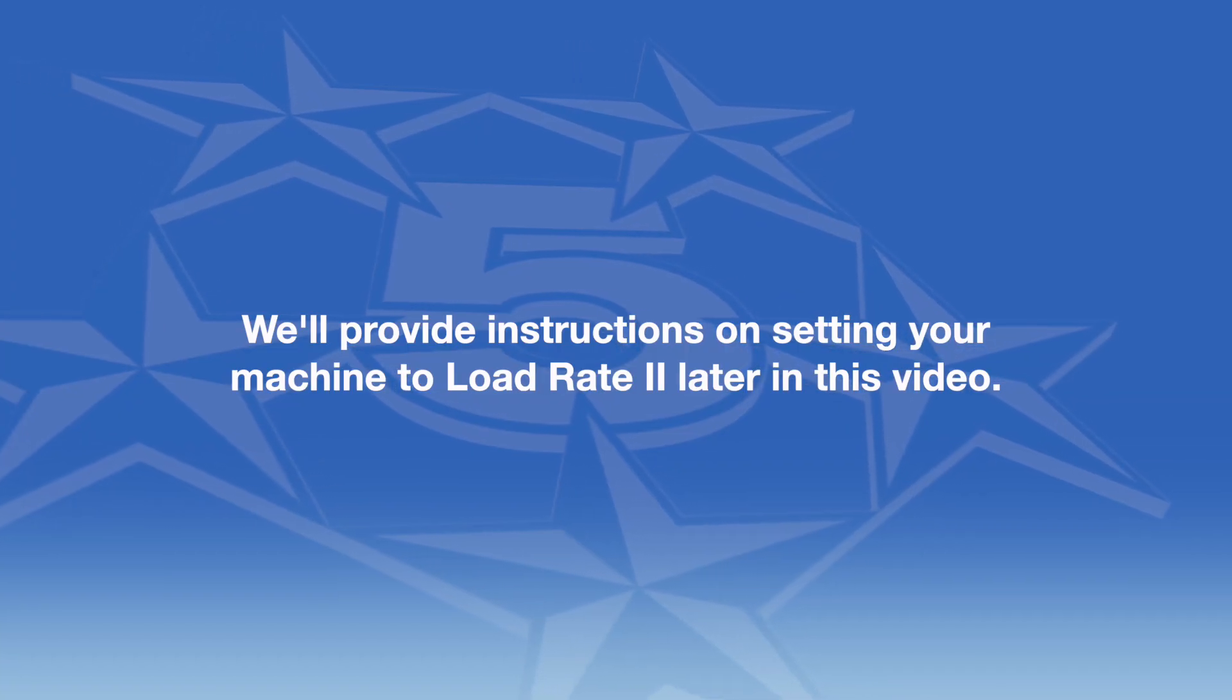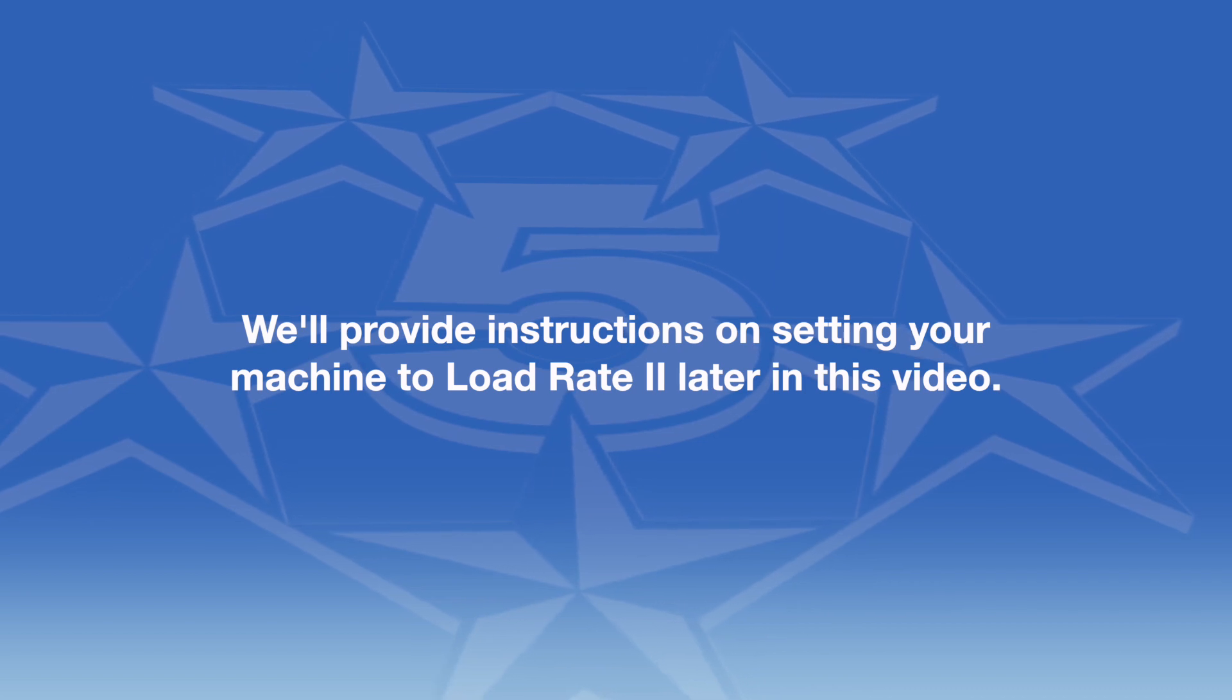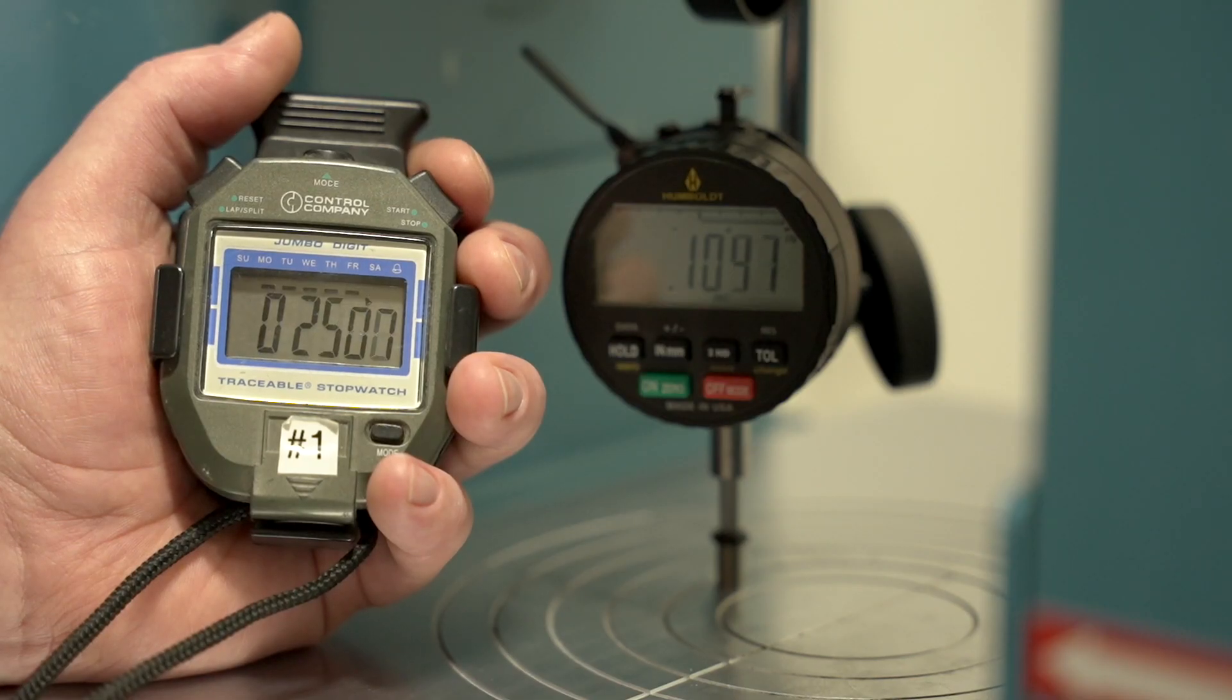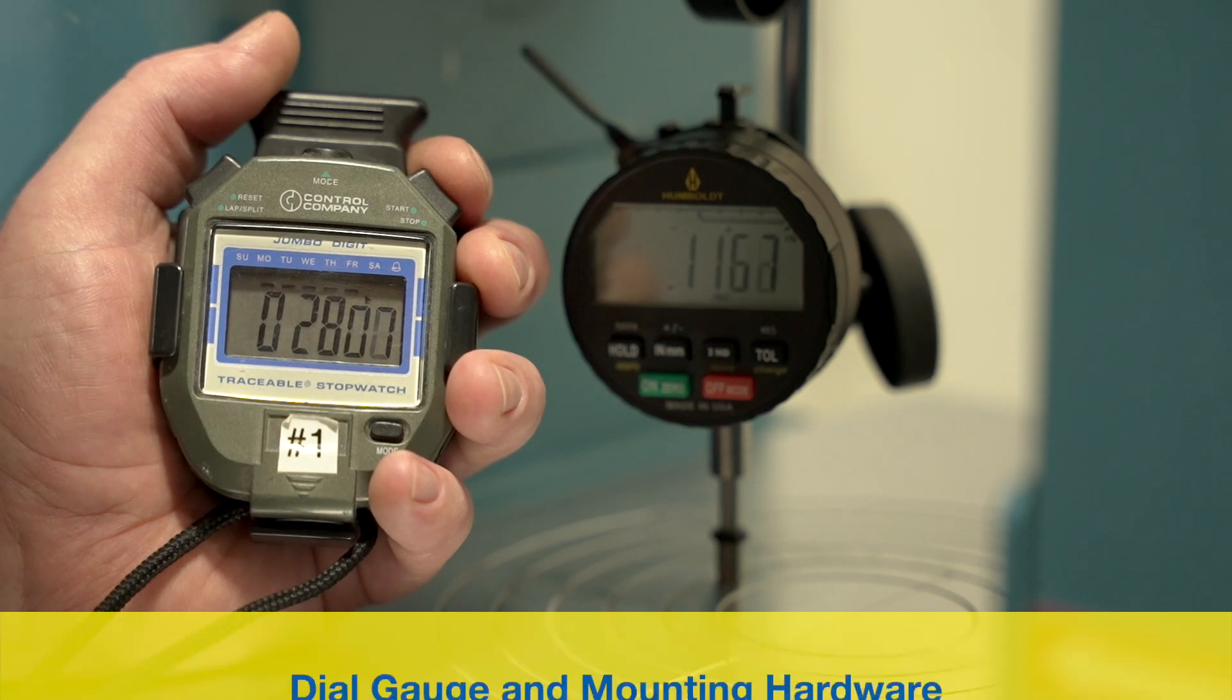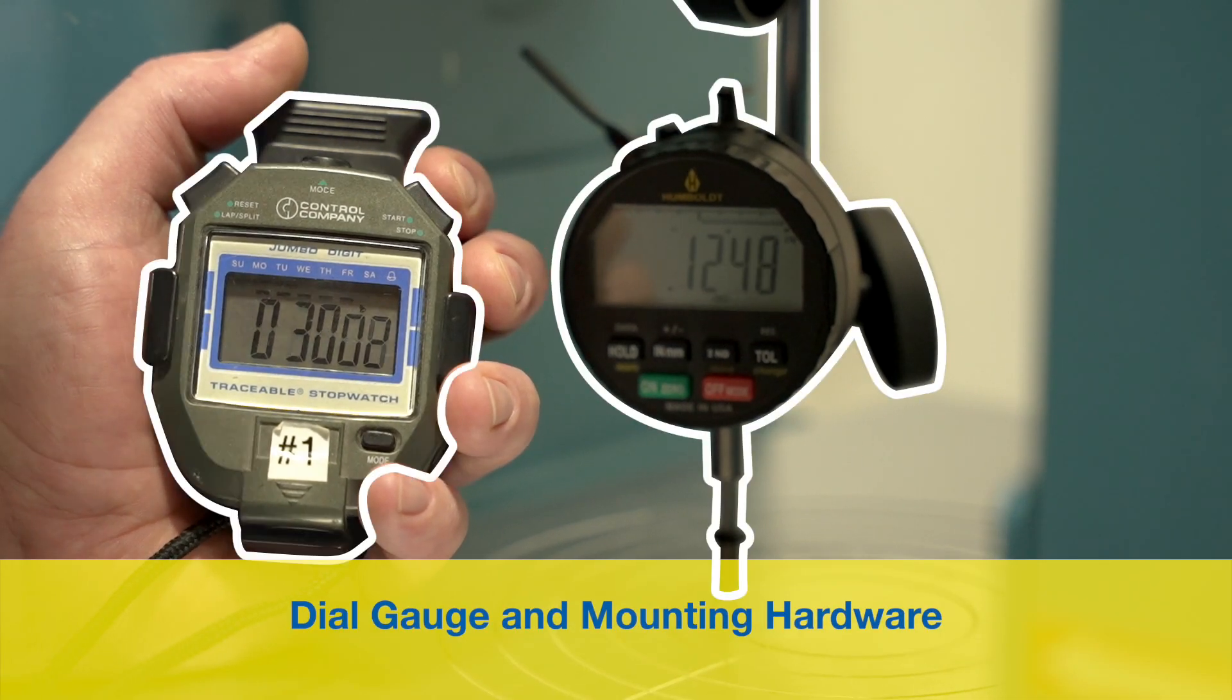We'll provide instructions on setting your machine to load rate 2 later in this video. If you plan to manually set your compressive testing machine to load rate 2, you'll need a dial gauge, mounting hardware, and a stopwatch.